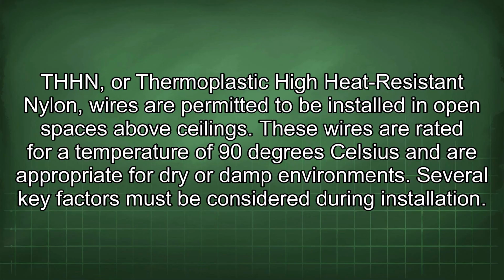THHN, or thermoplastic high heat resistant nylon, wires are permitted to be installed in open spaces above ceilings. These wires are rated for a temperature of 90 degrees Celsius and are appropriate for dry or damp environments. Several key factors must be considered during installation.